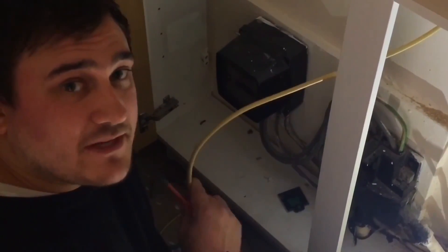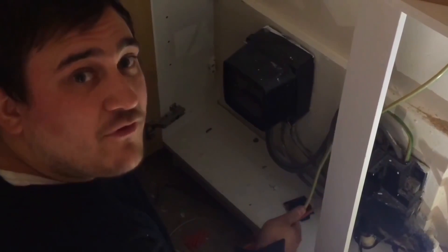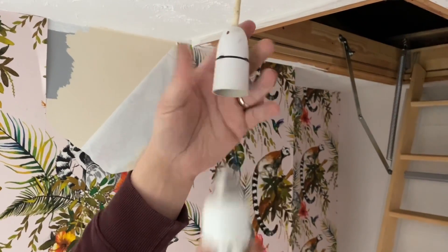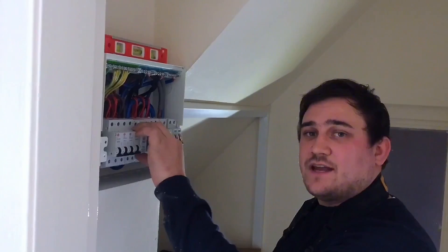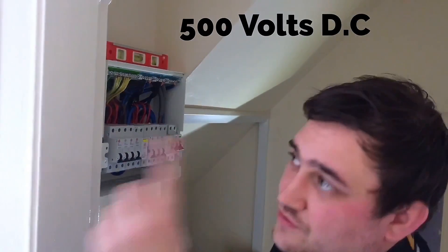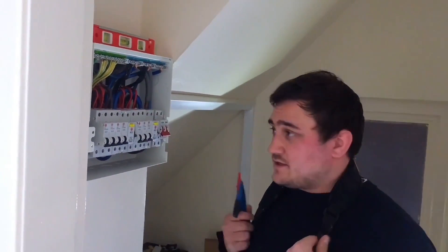I've just got to connect the 16mm squared earthing conductor to the supply authorities MET before I carry out my insulation resistance test. I've made sure all loads are out of the circuit, i.e. lamps, neons, anything plugged into the ring circuits. All RCDs are turned off because they have electronic components in, so that could be damaged by the DC voltage from the tester. The smoke alarms are battery, so we don't have to worry about them because they're not wired into the circuits.